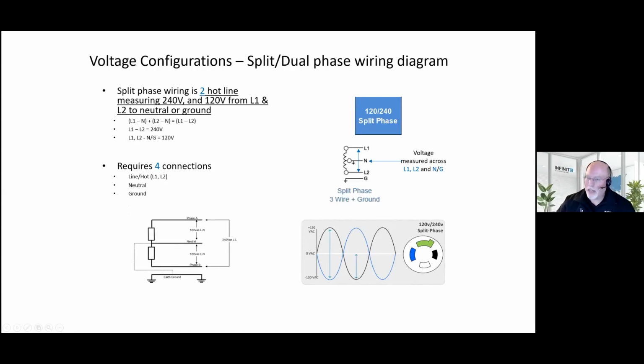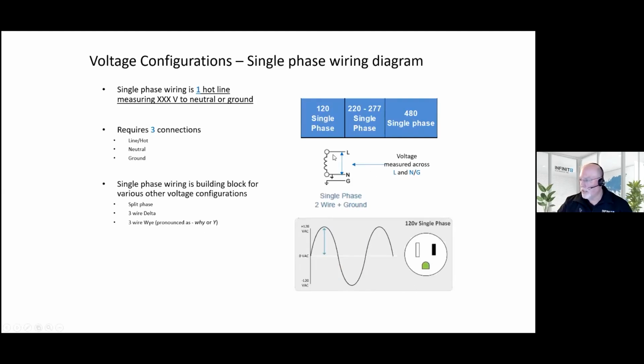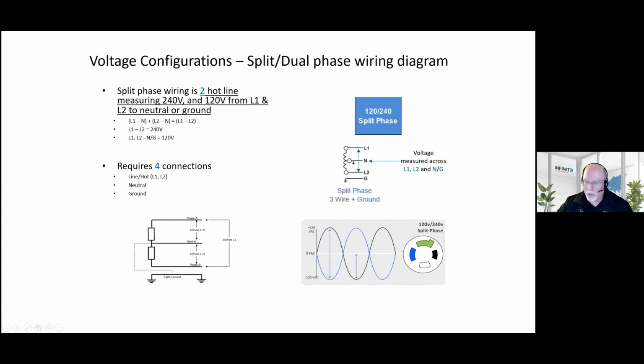So if I didn't ask that qualifying question, I would sell them a 240 volt single phase surge arrestor. They would get it and say, this is the wrong part, because you really wanted a 120/240 split phase. And in terms of the surge protector, language matters. If it's 1 phase, it's 1 phase. If it's 2 phase, it's 2 phase.